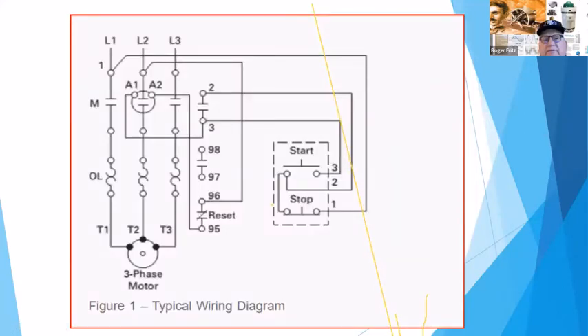The initial ways of starting most motors were basically just contactors. This shows a regular magnetic starter contact. It shows it basically has the 3 sets of contacts here that are connecting the 3 phases to the motor, and they just simply turned it on. The disadvantage to that was the motor actually would have a minimum of 3 to 6 times the running current. So if the motor is rated at 100 amps, it could take as much as 600 amps to start it. Well, you would have to have a much heavier generator in order to get that done. So the power companies came in and said, look, you can't start many motors across the line.